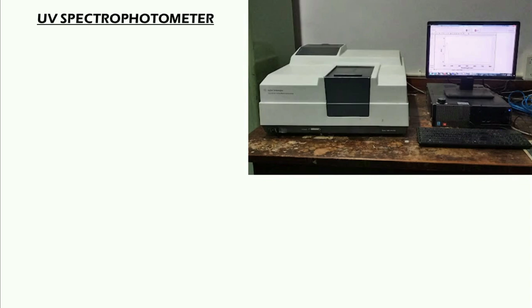So how is this sample treated inside this UV spectrophotometer? There is one light source. From there the light is transferred, and one collimator is there by which the light is passed and meets at one point on the prism, and from the prism there is a wavelength selector by which one light comes out and directly penetrates the cuvette and finally hits the detector, and the detector detects the absorbance of the particular solution or sample, which is shown on the computer.